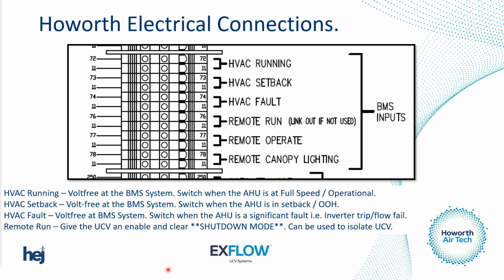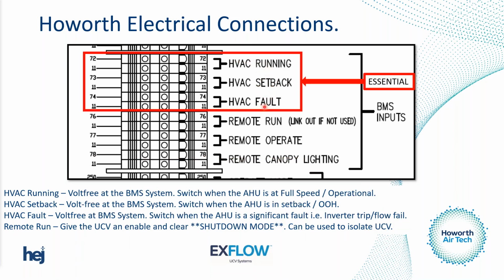So how do we do that from an electrical point of view then? This is a standard configuration of a Howorth electrical connection inside our power distribution panel. And these 3 sets of connections here, HVAC running, setback and fault, are all essential. So the UCV canopy must know when the HVAC is running at full speed, and it enables us to then go into full speed and setback.